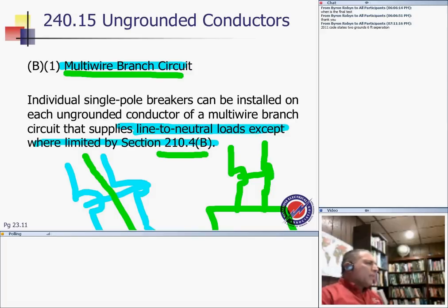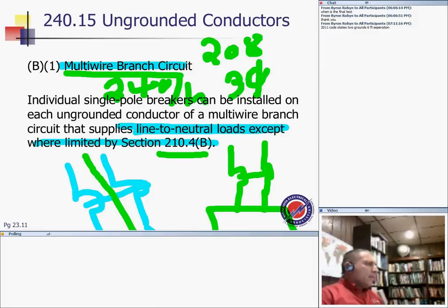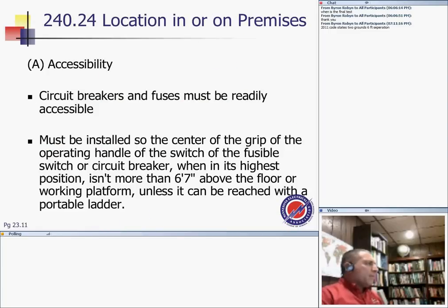You can feed up to 208 with some exception. 208 three-phase. And 240 single phase, 240 single phase. You can use an AC unit here and feed it from single-pole circuit breakers tied together. I'm not going to go there because there's some exception and so forth.